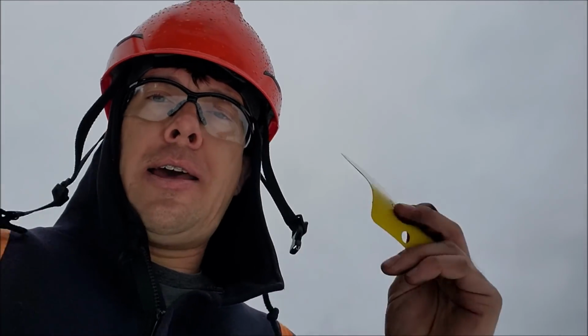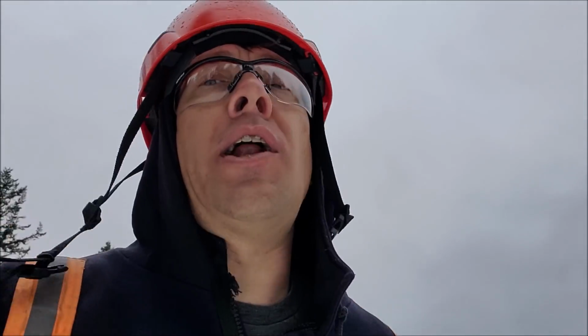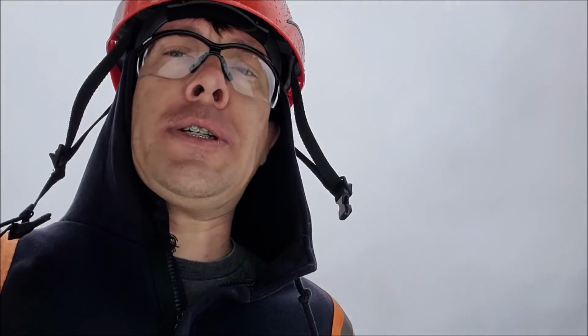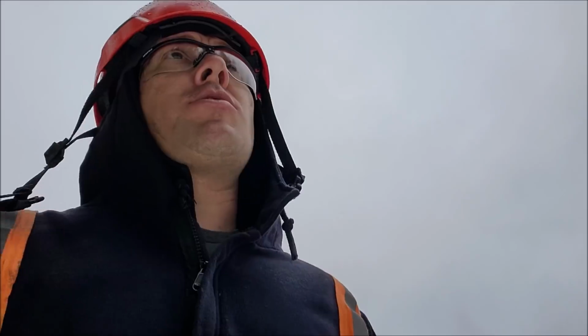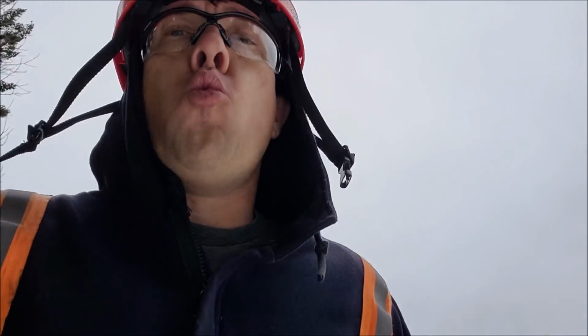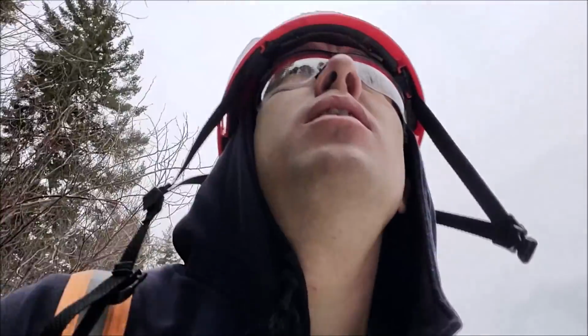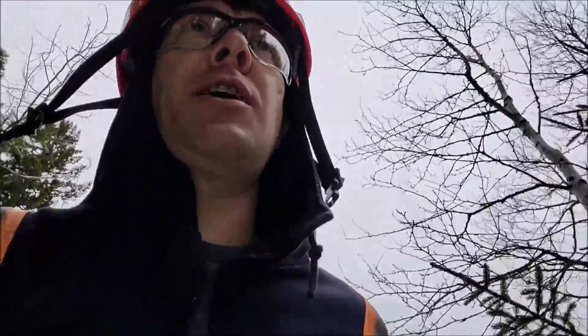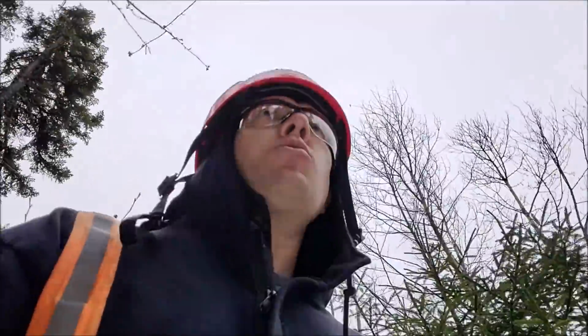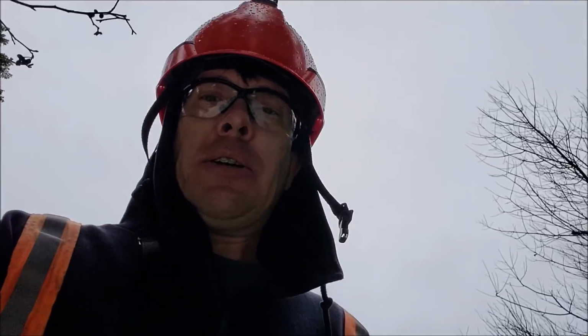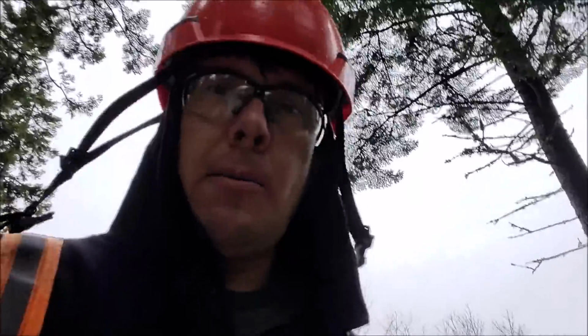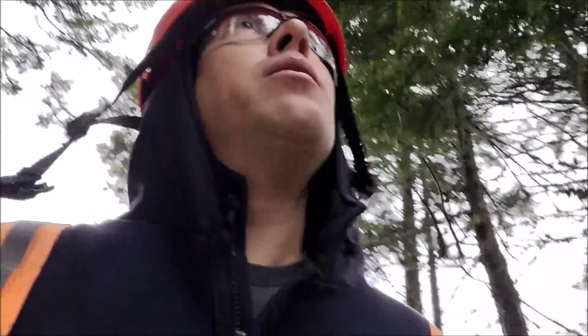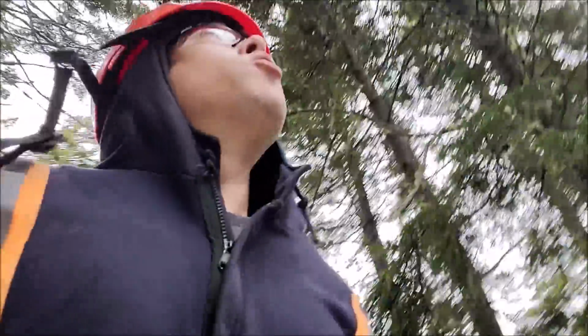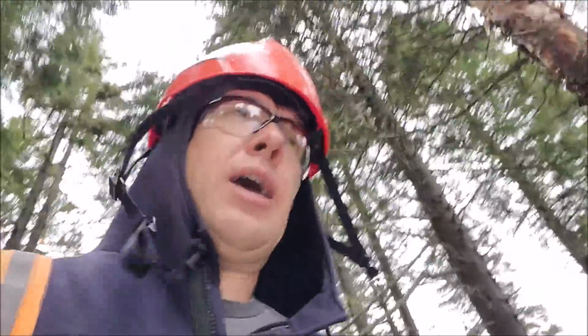We're going to put this tag in the field as well, right on the switch pole, and remove the doors. That way, as a fail-safe, if someone comes along and wonders why that's open, I grab this tag off the pole, which is weatherproof - it's got a vinyl that sticks over top once you mark on it, so the rain doesn't bleed the ink. We're going to install that on the pole here and head back into town.